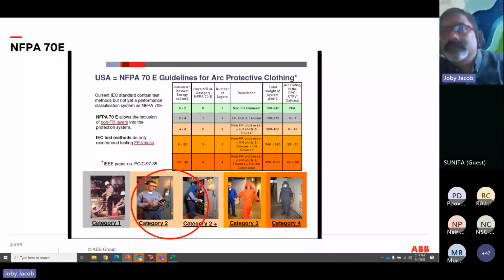If it is more than that, for example, if the incident energy is more than 100 cals, and particularly nowadays, everybody is fond of batteries, and a battery can produce huge DC arcs, right? So the incident energy could be very, very high. This is one of the biggest headaches we manufacturers are facing nowadays. How will you protect people from such huge DC energy, where, when all these string systems are connected in series, the incident energy can go much higher, where the PPE will not be able to cope? So we talk of automation in that picture.